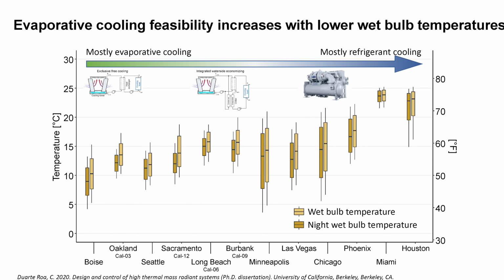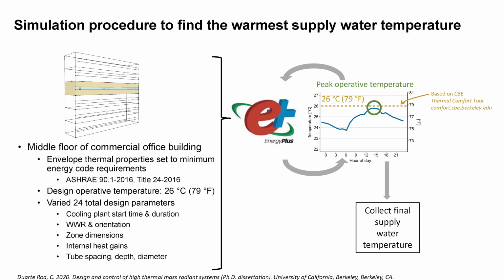And as I alluded to in the previous slides, wet bulb temperatures are not just one point. It's a distribution of temperatures that vary throughout the day, and they're usually lower during the nighttime hours. Here in this plot, you can see that we have a higher potential of using just evaporative cooling. As we move to the right, the buildings might be less so, and we have to use some more refrigerated cooling. But just by looking at the wet bulb temperature distribution, we can see that some cities might have evaporative cooling.